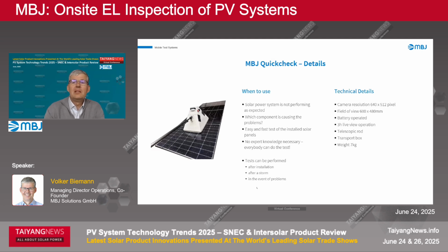Some technical details: we are using a very sensitive camera with 640 by 512 pixels. The field of view of this unit is 600 by 480 millimeters. So for a large solar panel of the latest generation, if you want to generate a full luminescence image of the entire module, you need roughly 12 positions.